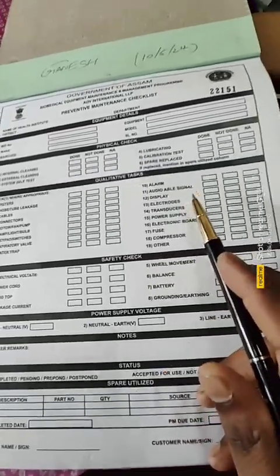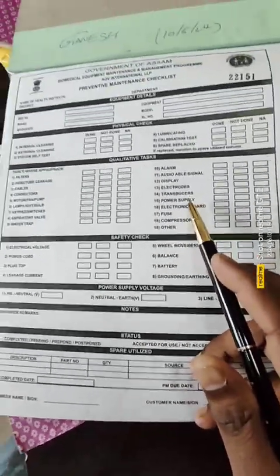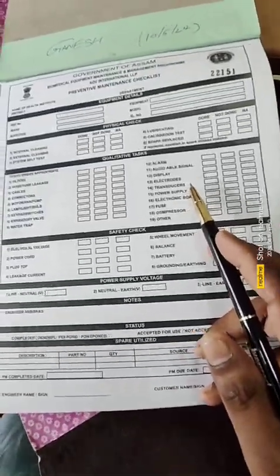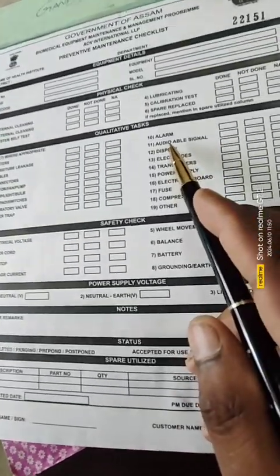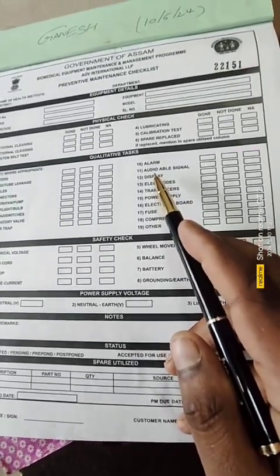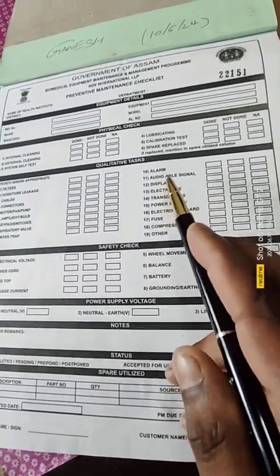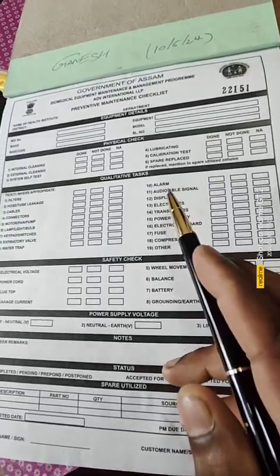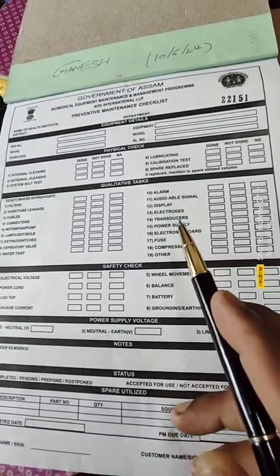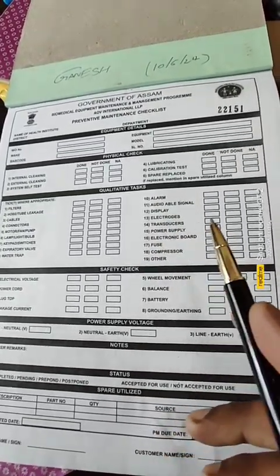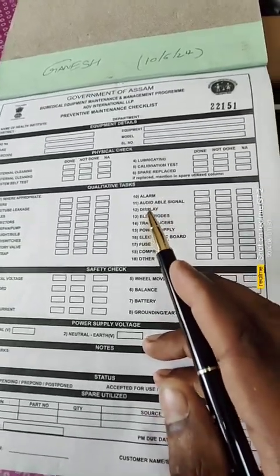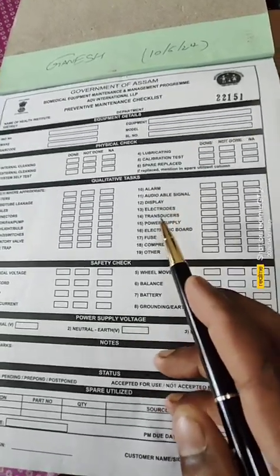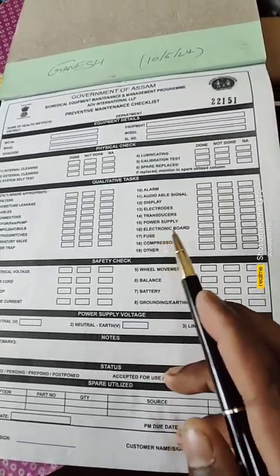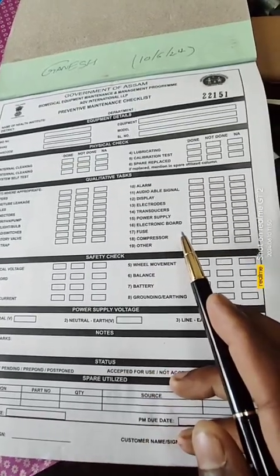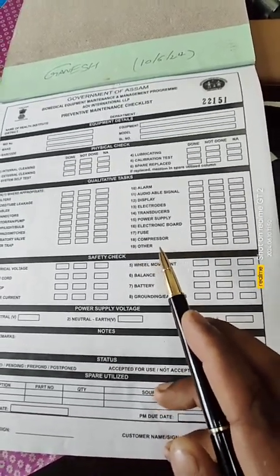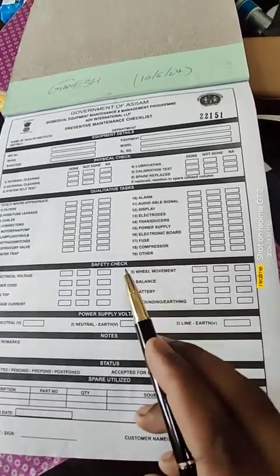Next, alarm available, because whenever operating the patient monitor, the alarm is the most important in the medical sector, and especially in ICUs, because based on alarms, with high, low and medium priority, the patient will be alert and the nurse will be alert. Okay, right. Next, audio signal available or not, next, display, electrodes, transducers, power supply, and electronic board, fuse, compressor not available in the patient monitor. Next, other things.